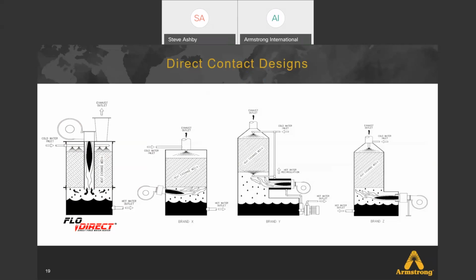Call that a flame tube, and that flame is extinguished completely before it gets to the end of the flame tube. So only the hot gases come out of the flame tube and then move vertically upward where the heat exchange takes place. And that's a critical point to point out, because if you look at the other designs here, everyone comes from the sidewall and they flame quench versus heating with exhaust. And there's a significant water quality improvement when you heat with the exhaust versus flame quenching.